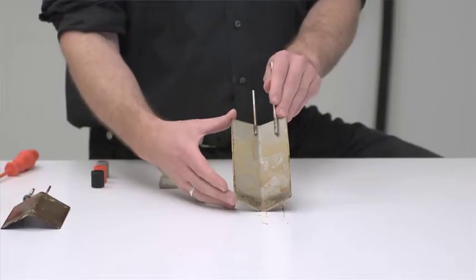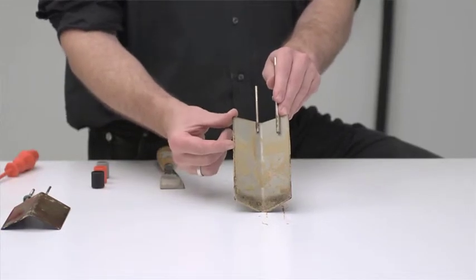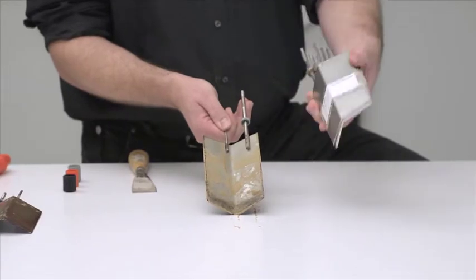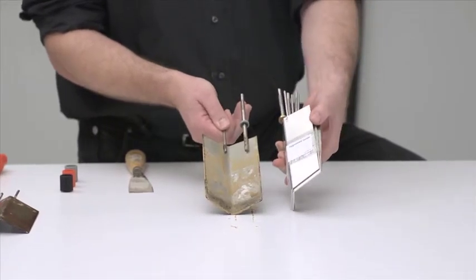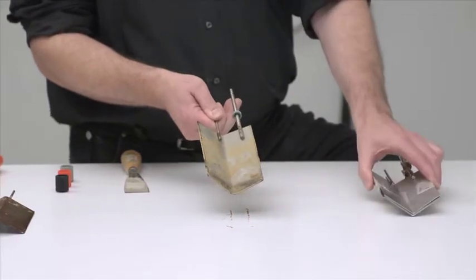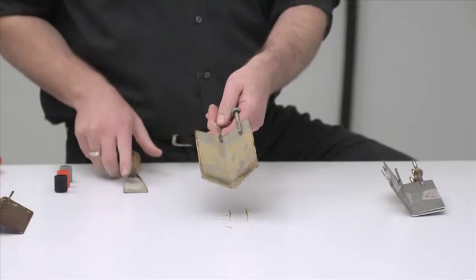The other criteria for maintenance would be the length of the electrodes. We always say, when the length of the electrode has reached just one-third of the original length, then please replace. I have here for comparison the original electrodes, which are also included in the maintenance set. You can see, there is actually not any electrode wear present, and in view of this fact, I have decided I will simply clean the electrode and then reassemble them.